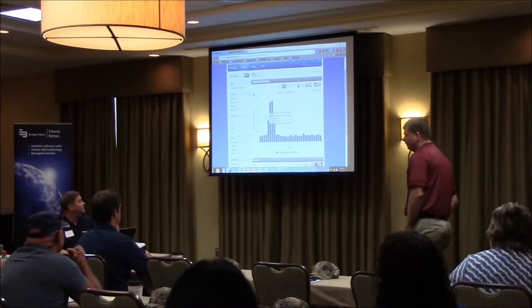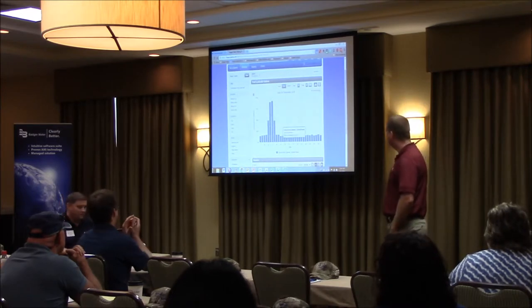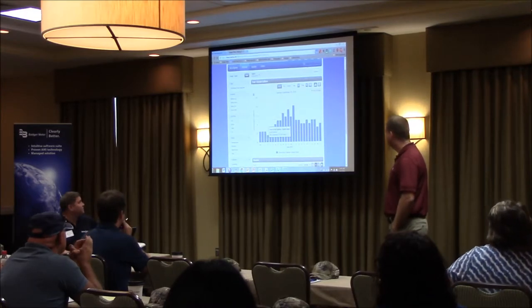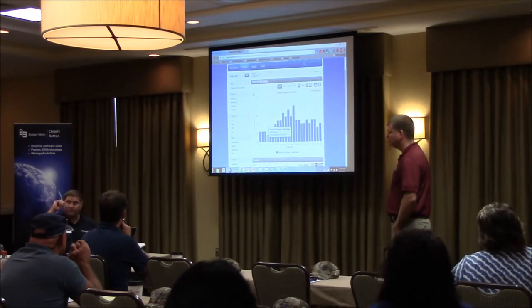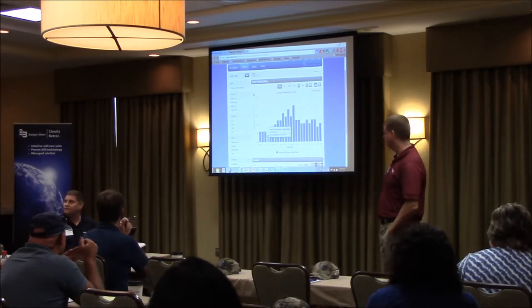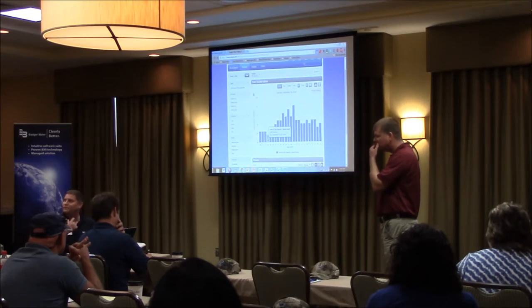And this is that account. Again, you can see this is the leak from the wastewater plant. It showed up on their meter as well. But when you look at this, this is their hourly usage. And again, our resolution is 1,000 gallons. So we know they get down to 2,000 gallons an hour. But incrementally, how much smaller? I think that one of the things that could probably help us with this is to implement the 15-minute resolution on this. So intrigued about getting that deployed on this one.